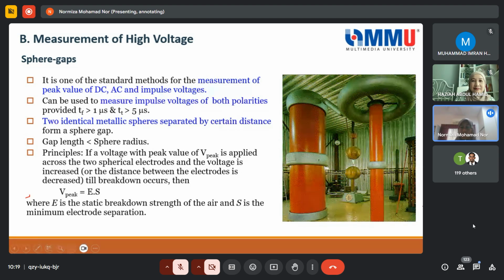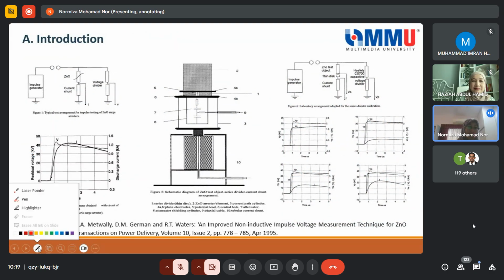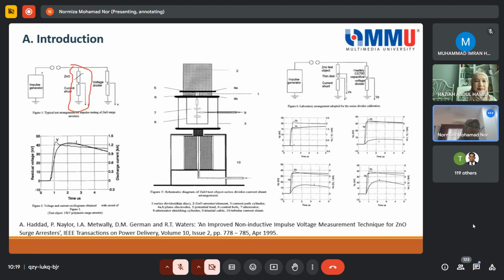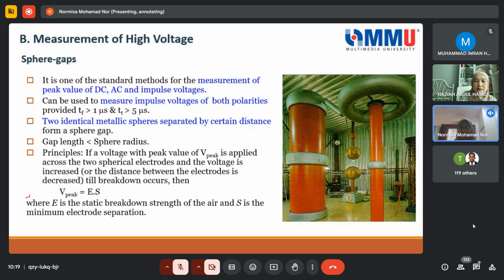All right. Actually, I want to show that when we do the measurement, especially if you want to know whether it is accurate or not, before we put the test loop, you can remove this part. So directly from the impulse generator to the voltage divider. What this diagram shows is exactly that: you have this resonance transformer, I think you've covered this in the generating of high voltage, and then this is directly to the measuring device without any loop here. And if you want to do calibration, you can also connect it to the capacitive divider just beside this. So you have two measurements of voltage, one from the spark gap and another from the capacitive divider.